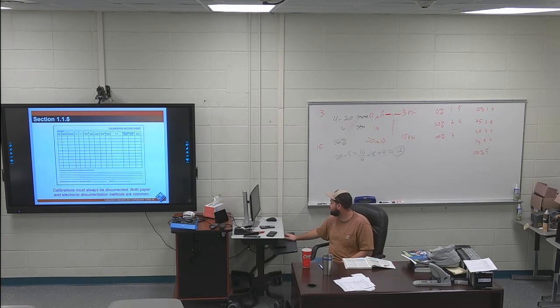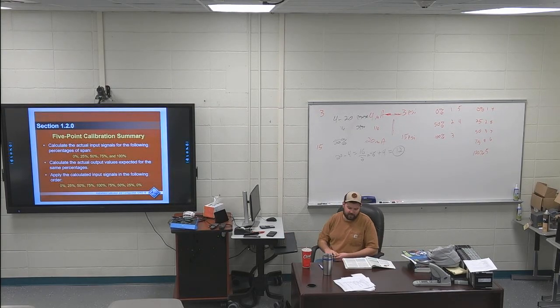Moving on to 120, 5-point calibration. I've got the first sentence highlighted, but this is what I talked about before. First sentence of 120: when performing a 5-point calibration on an instrument, the instrument's output is checked for accuracy and proportionally against the input signal, that is 0%, 25%, 50%, 75%, 100%, 75, 50, 25, 0. In that order. Everybody good with that?